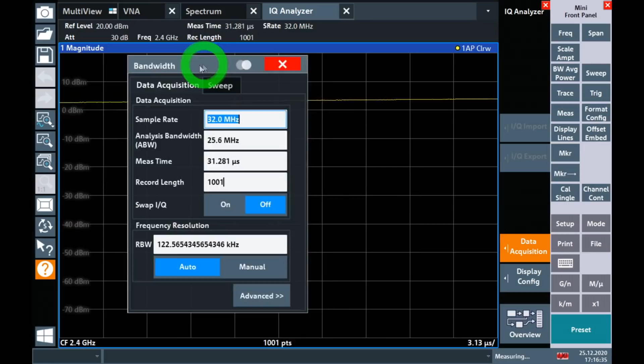Let's go under data acquisition here. Now under data acquisition, you can adjust the sampling rate, you can adjust the analysis bandwidth. We're looking at 25 megahertz here. But you can also go under the advanced menu, and now it gives you full flexibility on how the FFTs are calculated, how much overlap there is, what the total processing length is. These are pretty handy if you want to capture a rare event, or if you want to figure out how that event is spread across time.